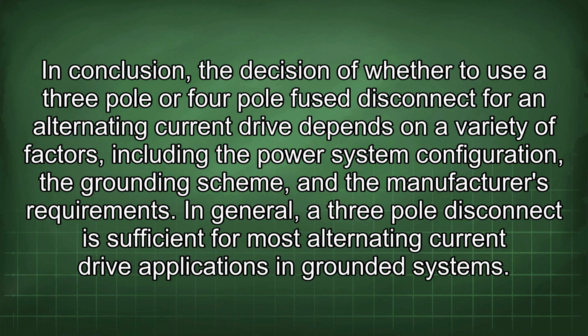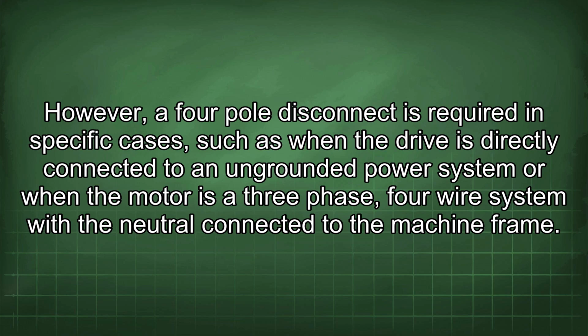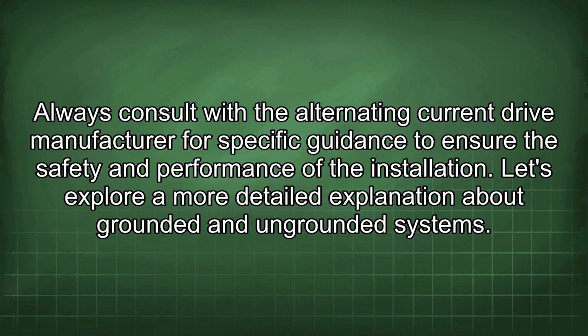In conclusion, the decision of whether to use a three-pole or four-pole fused disconnect for an alternating current drive depends on a variety of factors, including the power system configuration, the grounding scheme, and the manufacturer's requirements. In general, a three-pole disconnect is sufficient for most alternating current drive applications in grounded systems. However, a four-pole disconnect is required in specific cases, such as when the drive is directly connected to an ungrounded power system or when the motor is a three-phase, four-wire system with neutral connected to the machine frame. Always consult with the alternating current drive manufacturer for specific guidance to ensure the safety and performance of the installation.